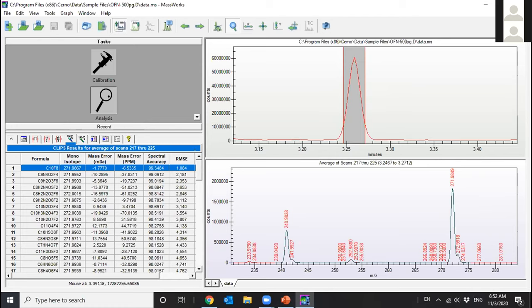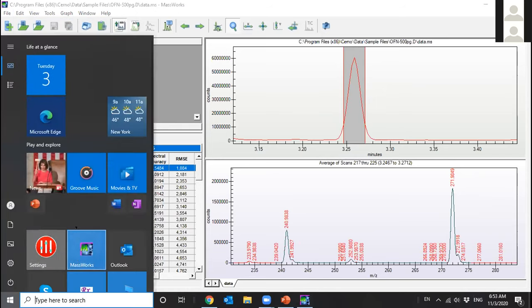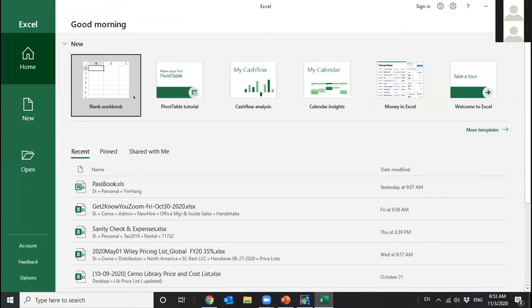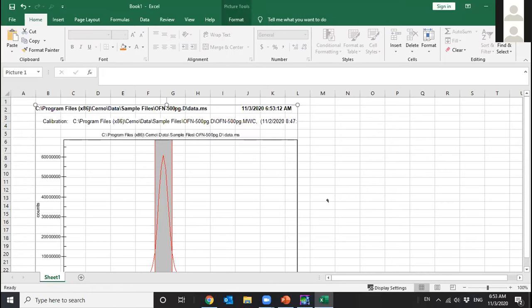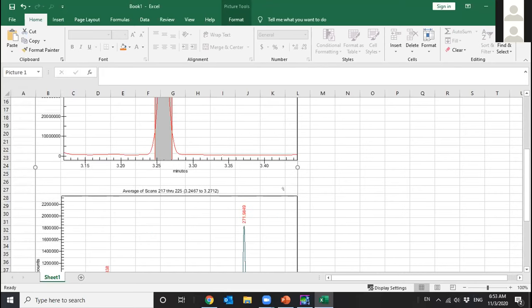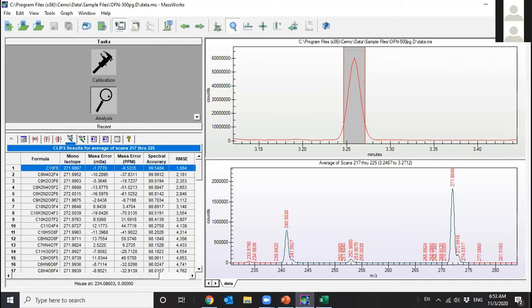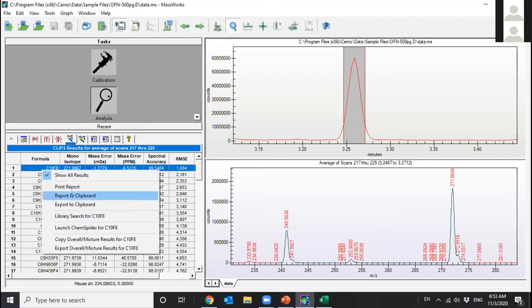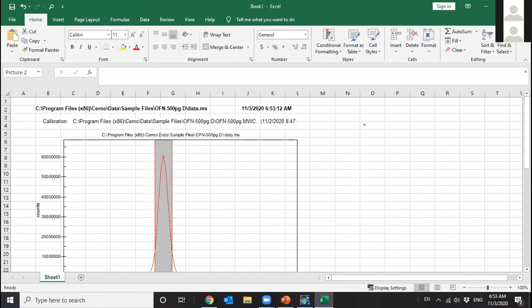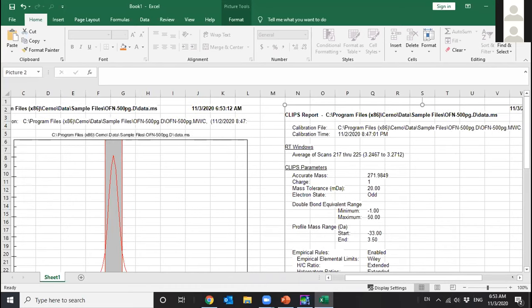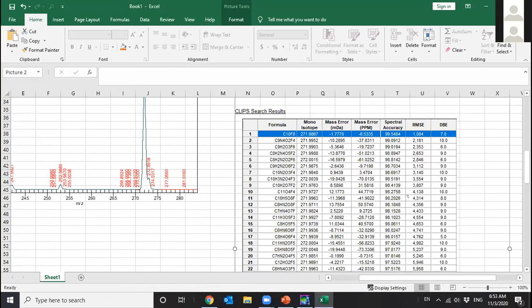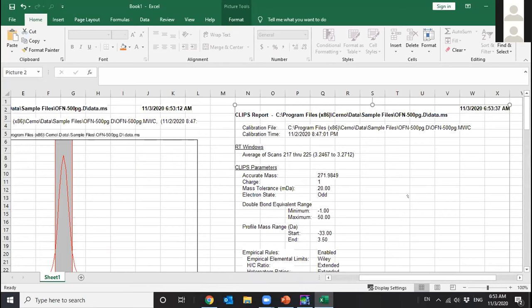Before I finish the GCMSD, I'd like to show you a couple of reports, a very simple reporting function that you can use for your records. If you want to get the images of the chromatogram and the mass spec, you can go to the edit menu and say copy report to clipboard. That would allow you to copy an image as a report, which should reflect the chromatogram, the spectral overlay and the mass spec. You can also send the report of the elemental composition determination to the clipboard, which would also create another image file, including the search conditions for the elemental composition, the date and timestamp, and the search results. So those are the two simple reports that you can save for your records.